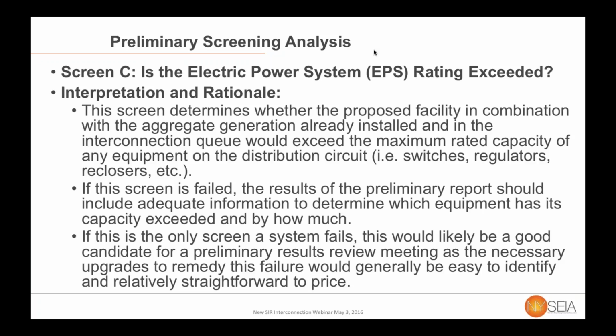There are several screens like this, so it's worth noting that when looking at whether you exceed the rating of any of the equipment on the line, it's the total aggregate amount of DG. So it is your application plus all of the existing generation already interconnected to that circuit, plus all of the generators in the interconnection queue ahead of you in the system. And therefore, that is what we're going to reference whenever we talk about the aggregate DG. It's those three pieces all added together.